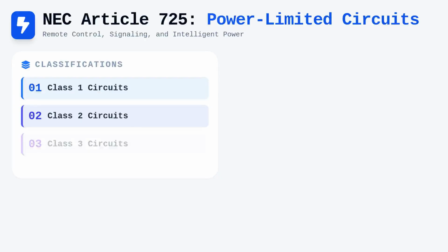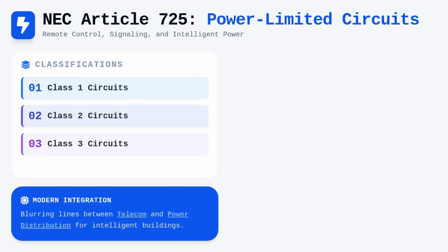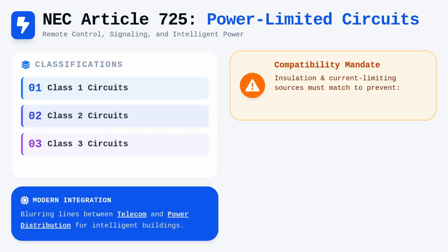Managing power-limited circuits requires a different set of rules, which brings us to Article 725. This section governs Class 1, Class 2, and Class 3 remote control, signaling, and power-limited circuits. In many modern intelligent building deployments, these circuits carry both power and data, essentially blurring the lines between traditional telecommunications and electrical power distribution. You must ensure that the insulation levels and current limiting power sources are compatible with the intended application to avoid overheating or arc faults.